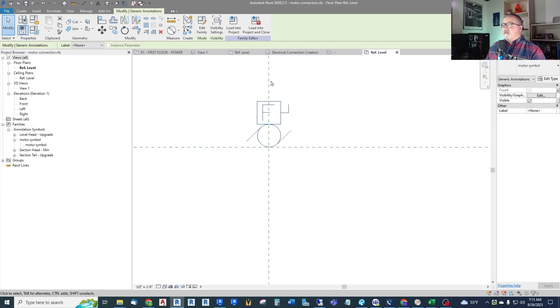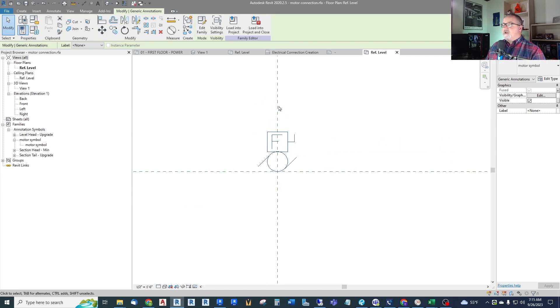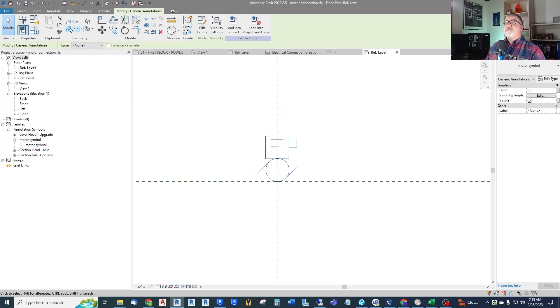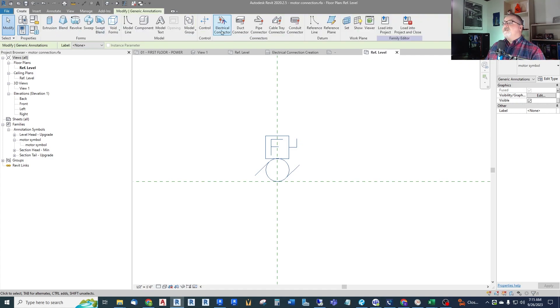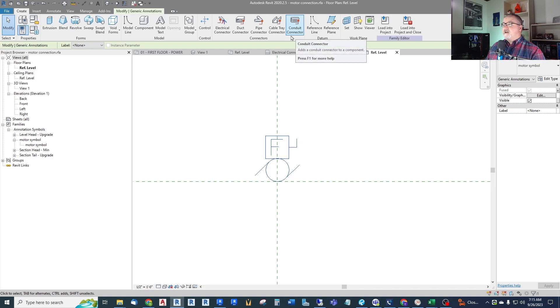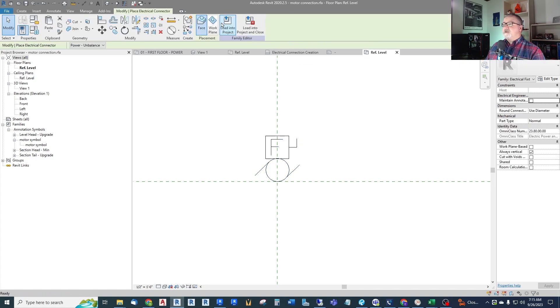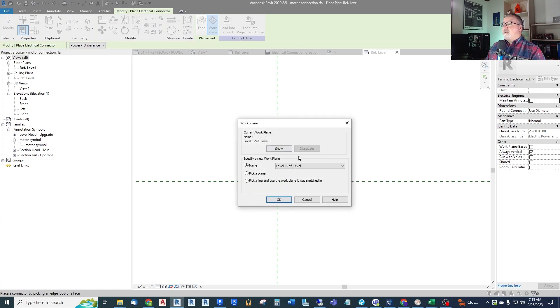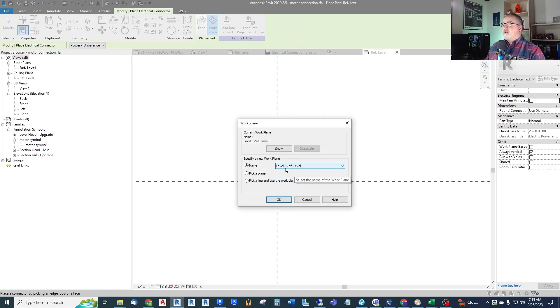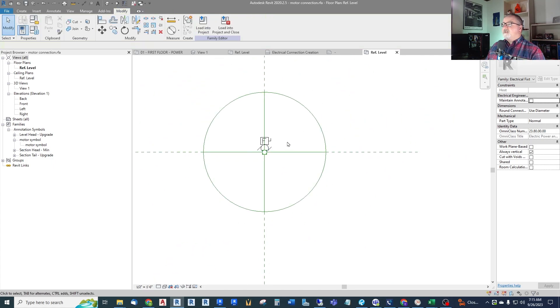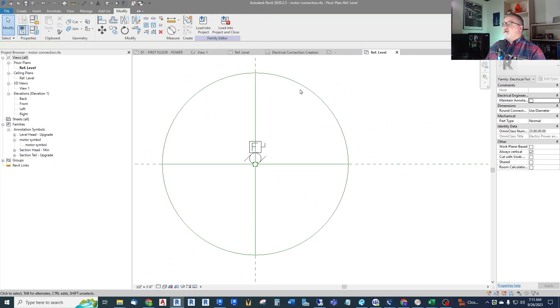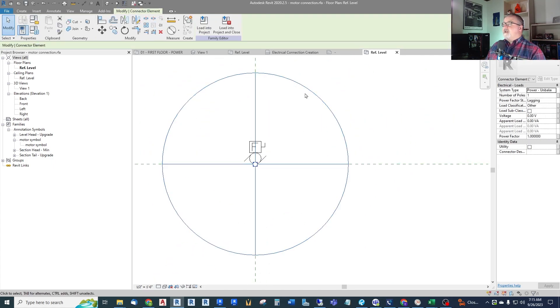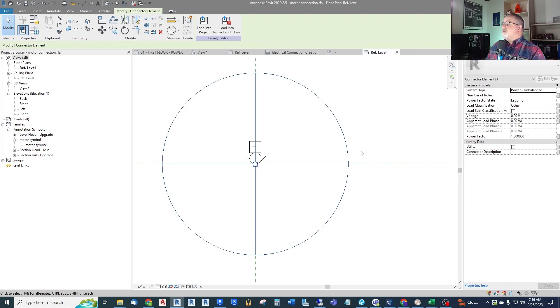Now we need to add the electrical connection to this family. So under create go over to electrical connector. We're not doing conduit connector, a physical conduit. We're doing a logical electrical connector. And it needs a place to land. So we pick a work plane and it'll say what work plane do you want? Well we have a few of them. I like to put it on the reference level. So it just shows up like the big green circle. Now we click on that and we have all of our electrical properties that come in an electrical connector. So what we're going to do is we want this to be a balanced load. So if we have a multi-phase load we want the load balanced on all phases. So go to power balanced.